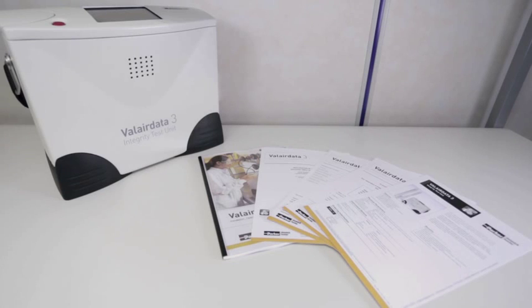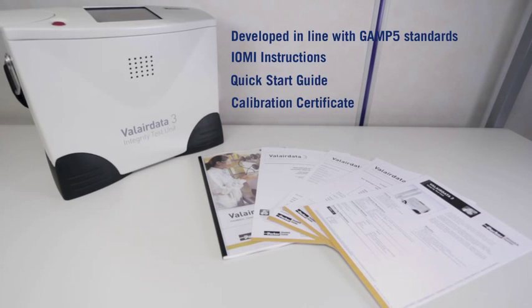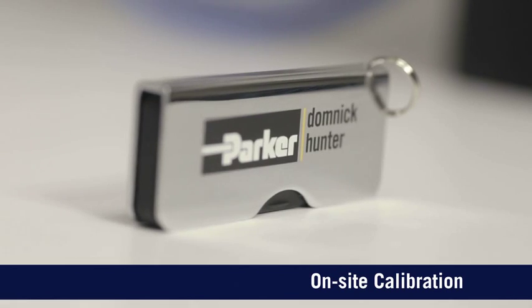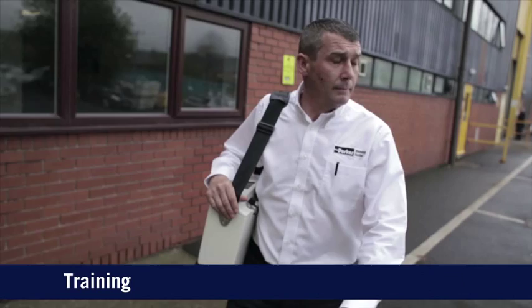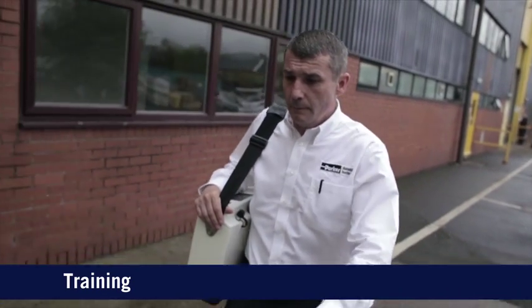The instrument has been developed in line with GAMP 5 standards and comes supplied with the necessary technical documentation including IQ/OQ instructions, quick start guide and calibration certificate. Parker domnick hunter offer full support packages including unit commissioning and operator training.